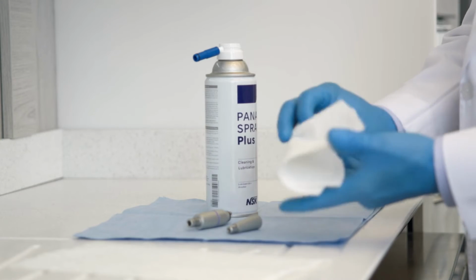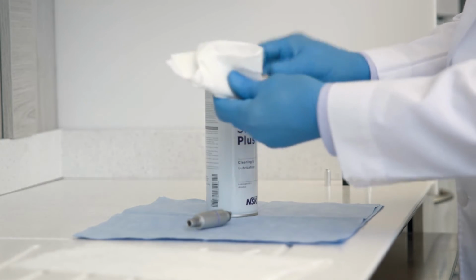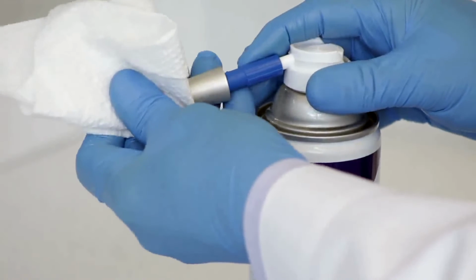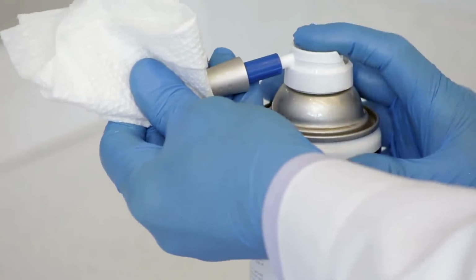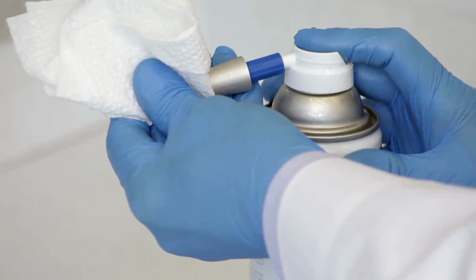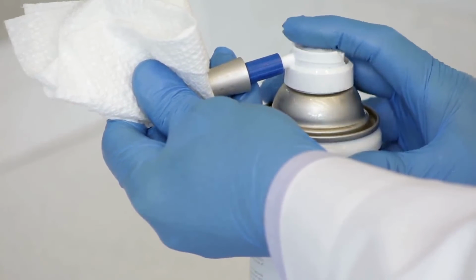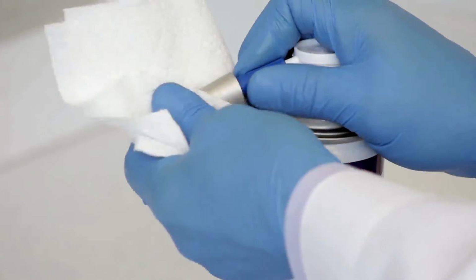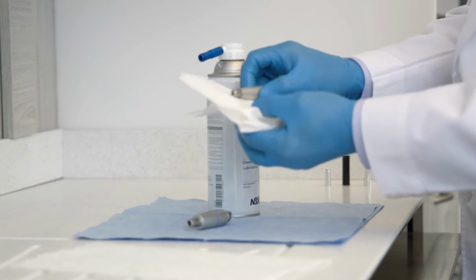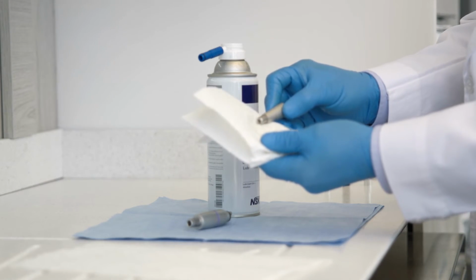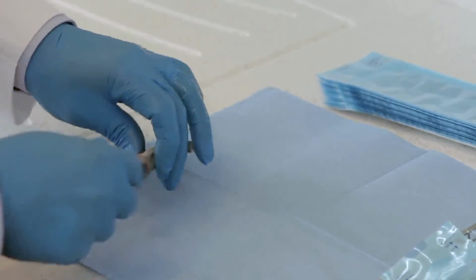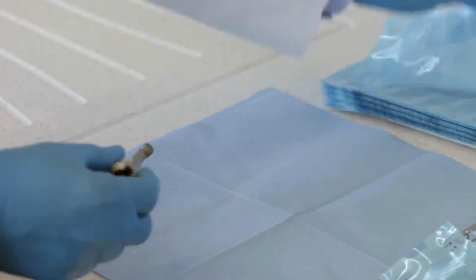Cover the nose cone properly using a paper towel. Insert the nozzle to the back of the iProphyAir nose cone all the way in and spray for 2 to 3 seconds until the clear oil comes out of the head. If you notice black debris coming out of the head, repeat this process again until the discharged oil is completely clear. Autoclave sterilization is recommended.